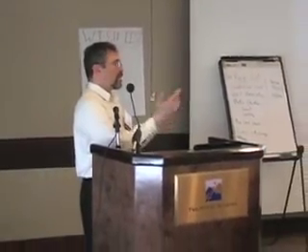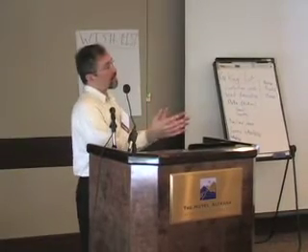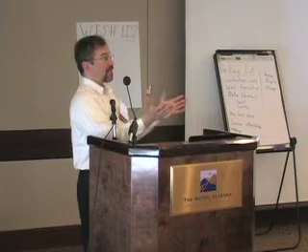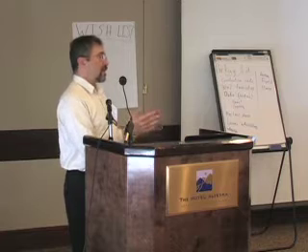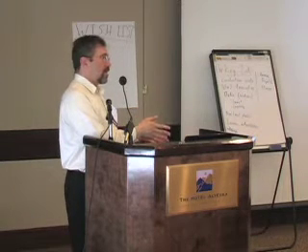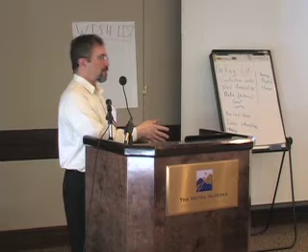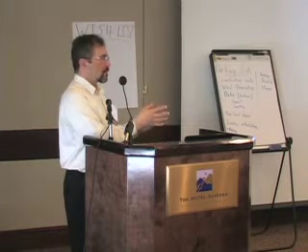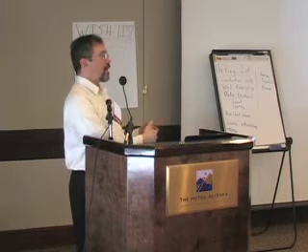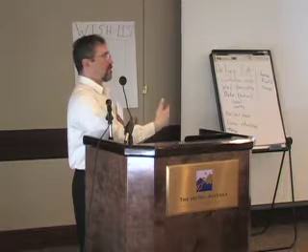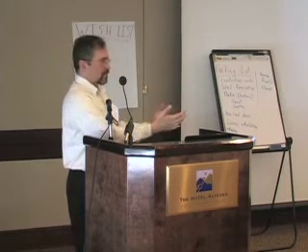The way HOMER is now, we can say, okay, given today's load, here's what the system should look like. Given what we think the load will be in, say, 5 years, here's what an optimum system would be for that load, and it'd be different, and we can compare them. We can also do an analysis that says, let's say we install the system that HOMER says is optimal for today. 5 years from now, we do another analysis as if it was 5 years later.